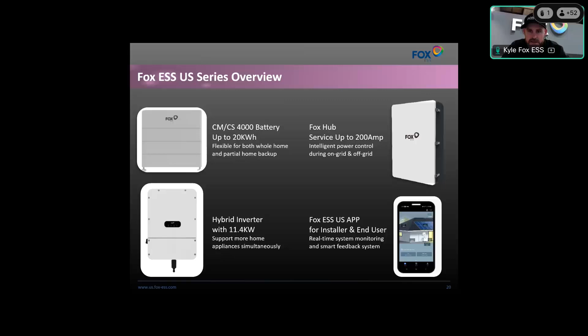As we discussed earlier, 9.6 or 11.4, you can AC couple it or DC couple it or both. We have an LRA of 160 amps, which is actually really high and effective, and this stacks when you have multiple in parallel. So if you have two in parallel, you're going to have 320 amps of starting load capacity, and it goes up from there.